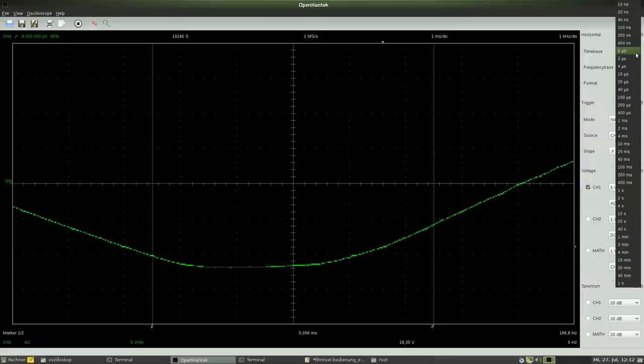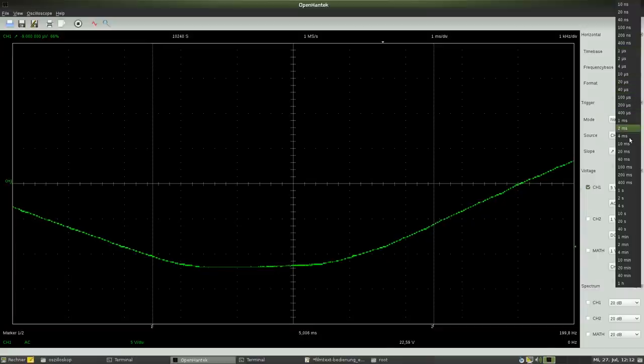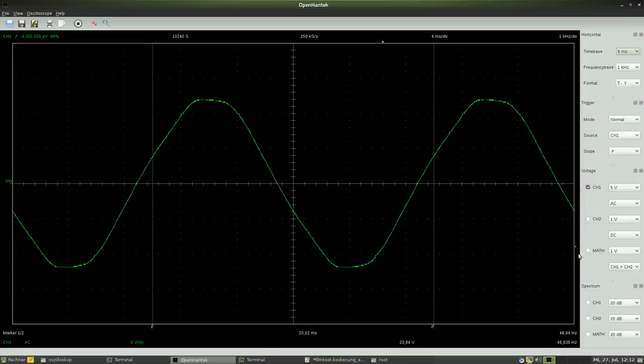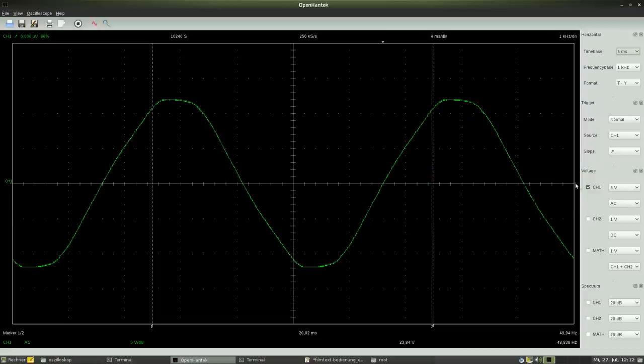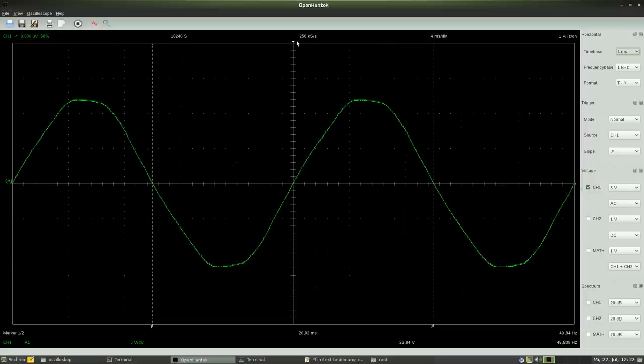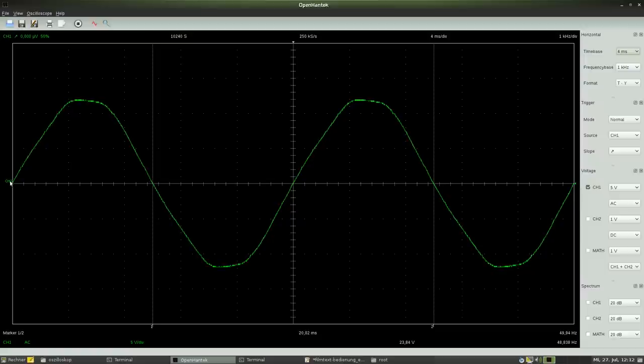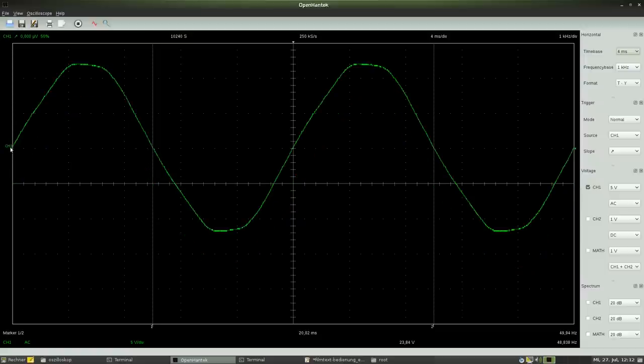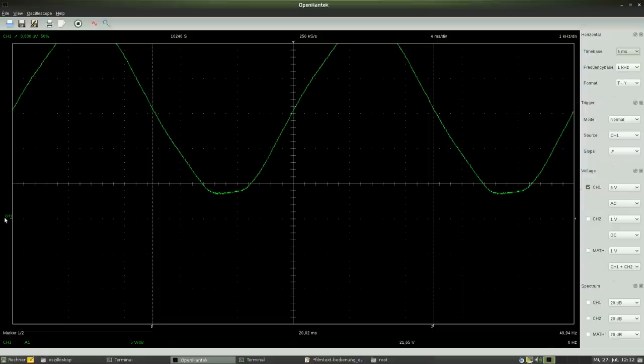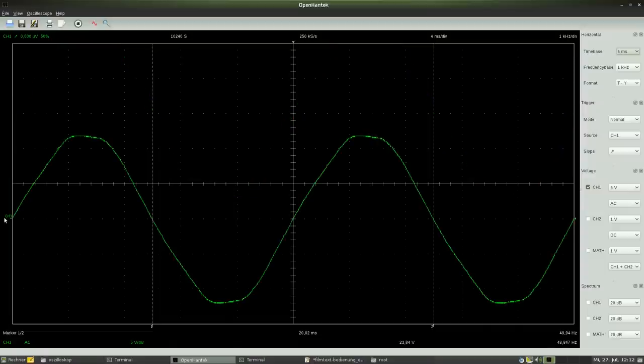The point of zero volt at the vertical axis can be adjusted too. Up to now the middle axis of the screen represented the line of zero volt. By sliding the CH1 symbol in vertical direction, this line can be moved along the Y axis. The position of the sine curve is moving in an accordant way.